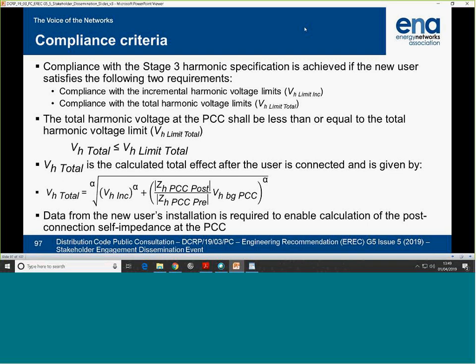And this impedance is the impedance we provided at the PCC without the customer, and this is the impedance of the same node after the customer is connected. It shows what impact the cable and other equipment had on this impedance. If the impedance at the given harmonic is raised, it means amplification. If it's less than this, it means the customer equipment is absorbing some harmonic.